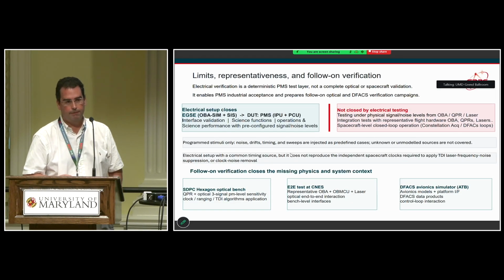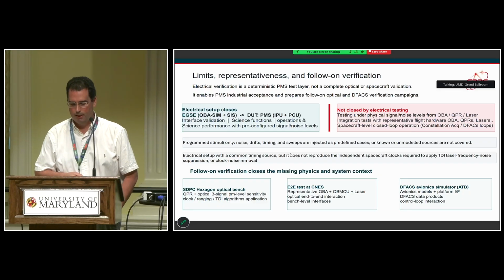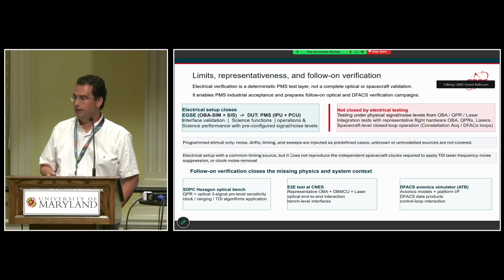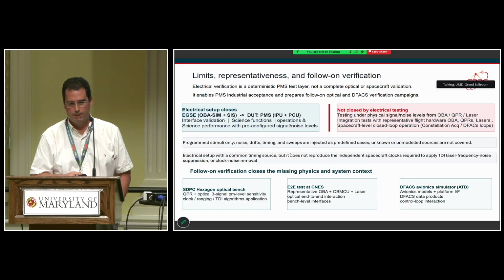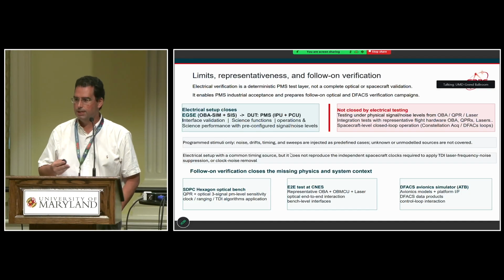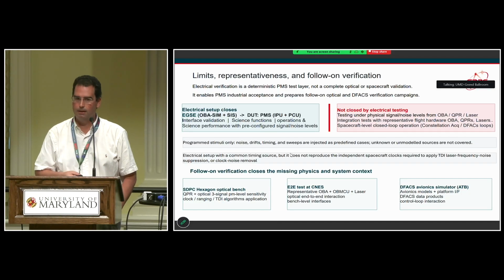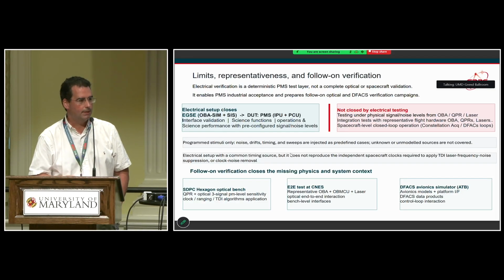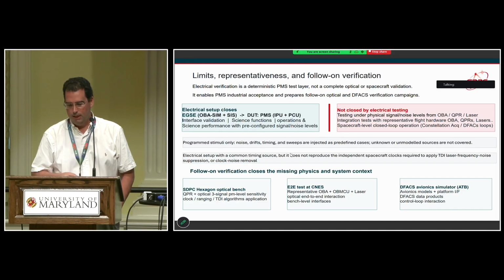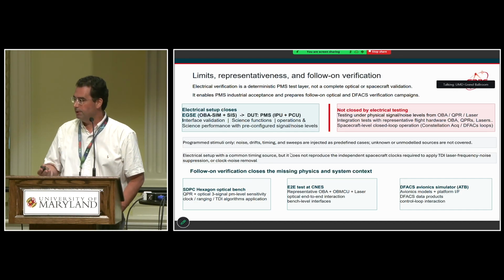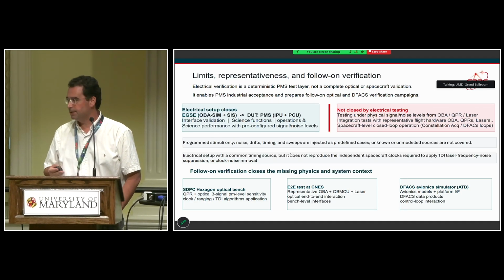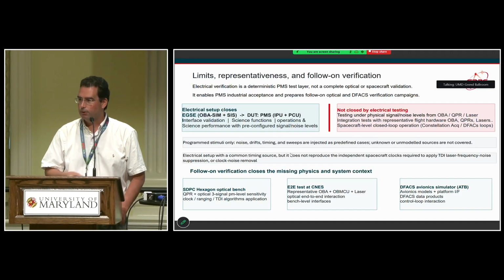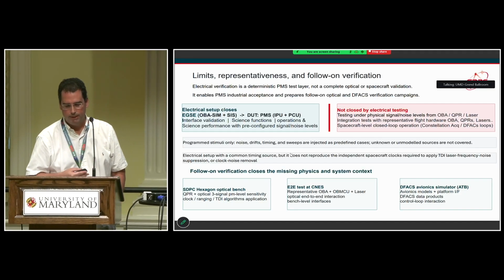But this electrical verification has several limitations in the representativeness of the instrument. Basically, the electrical simulator of this verification process is very deterministic. We can only synthesize noise levels and signal levels predictable from our best understanding of the performance models. So it's not fully representative of other noise sources that could happen on the optical bench, like stray light or microvibration effects and so on. So it's a very deterministic way forward for the acceptance of the PMS from the industrial contractor.